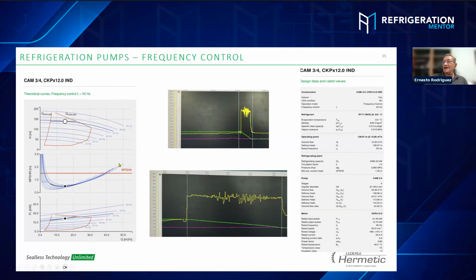I asked how many amps in this application. They said we have 32 amps. I said, no, no, no. You're overheating the pump. Go back to 52 hertz. This is a very good sample, because I see this a lot. There are VFD drives on pumps all the time. Glycol, CO2, it doesn't matter. We're talking about CO2. So we have a drive on this pump. You're saying that when you design a CO2 system, you're designing at a specific hertz, so that flow is going to stay the whole time.